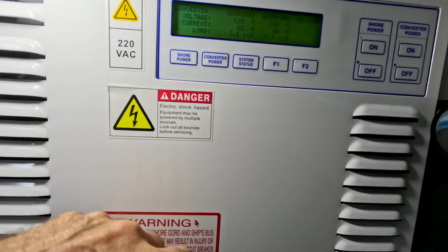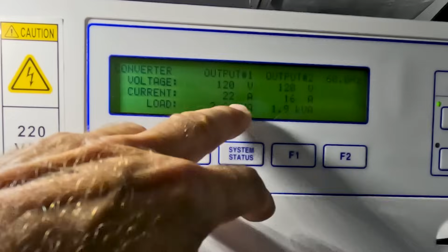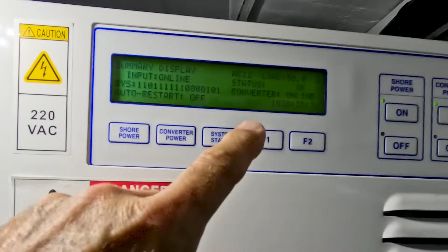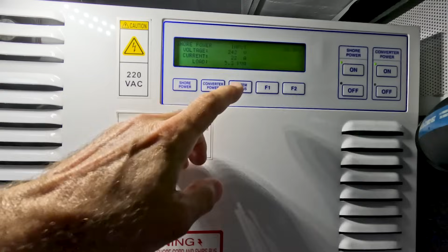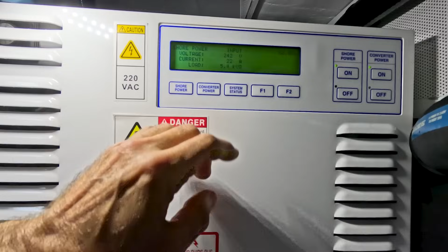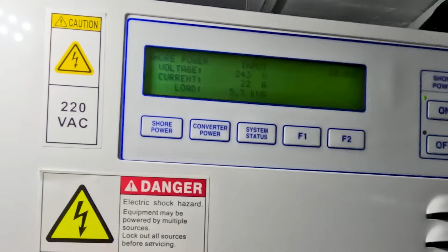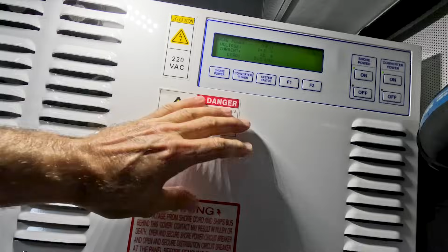We got the converters. We just turned the generator off. 22 amps, 16 amps on output, leg 1 and leg 2, and load is 2.6 kVA and 1.9 kVA. System status all looks okay. Load is at 50%. This is an AC-12. Shore power, we've got good input of 242. Everything's 60 hertz, and the current they're drawing right now is 22, so you've got a total of 50 amps, so we're roughly half.